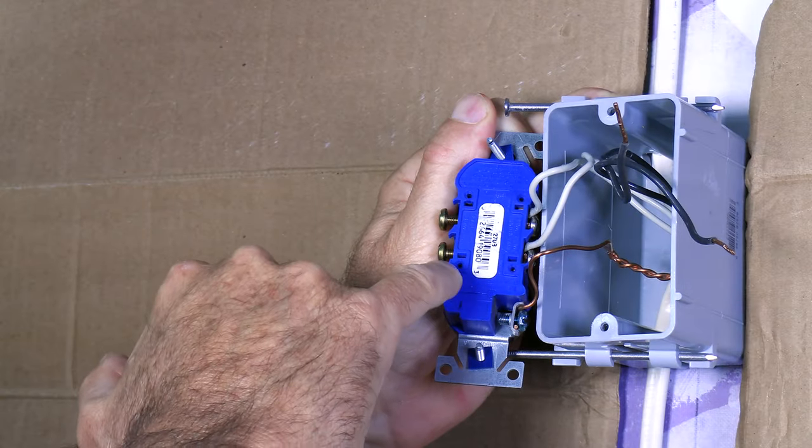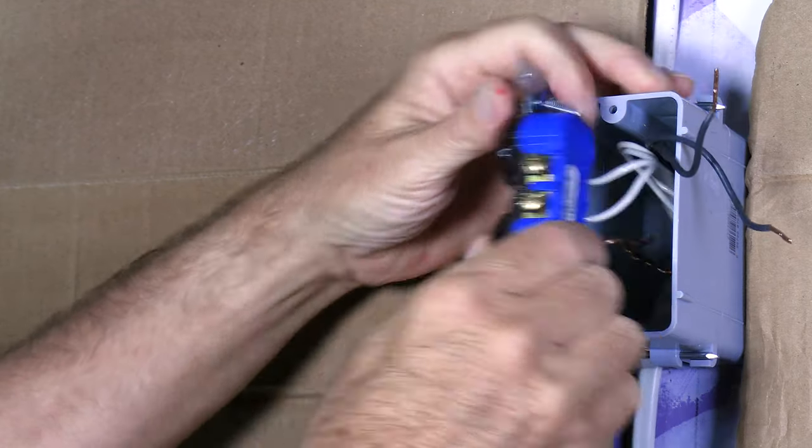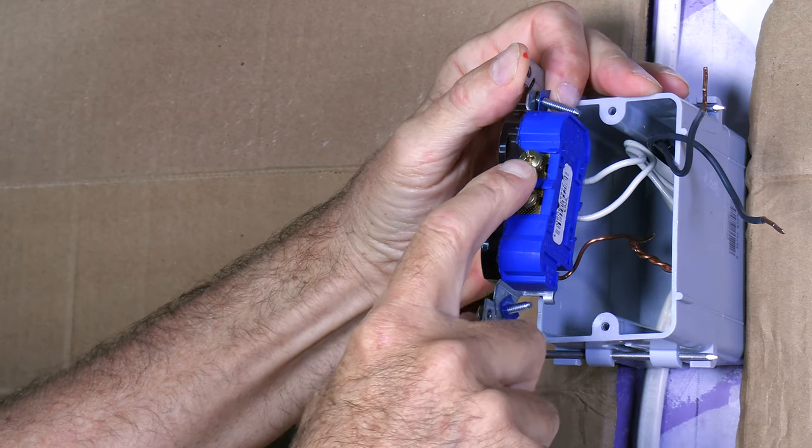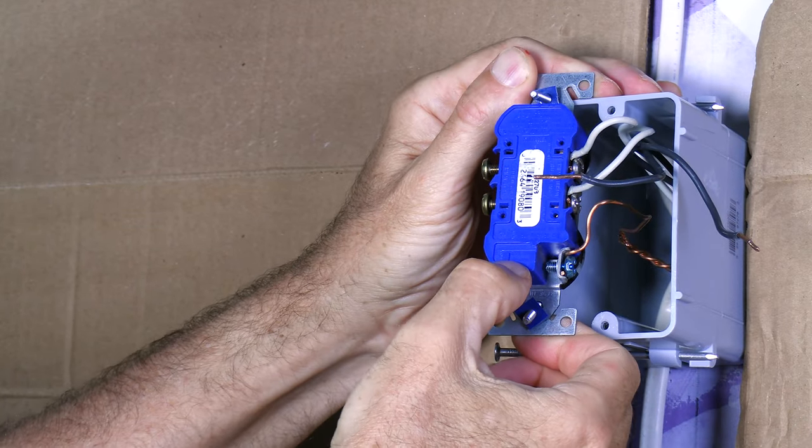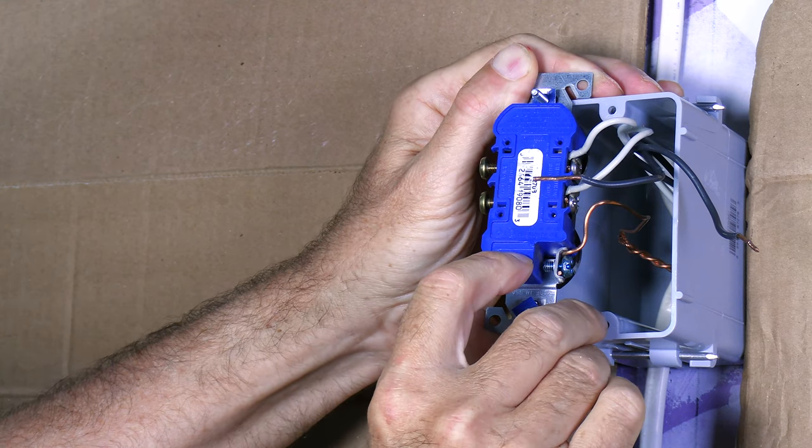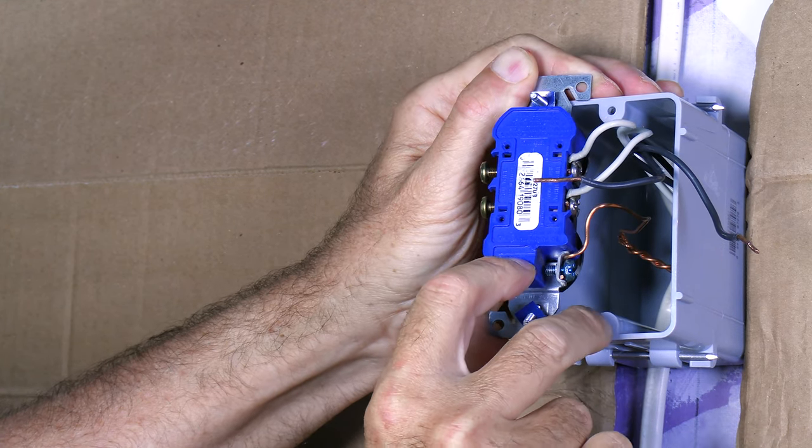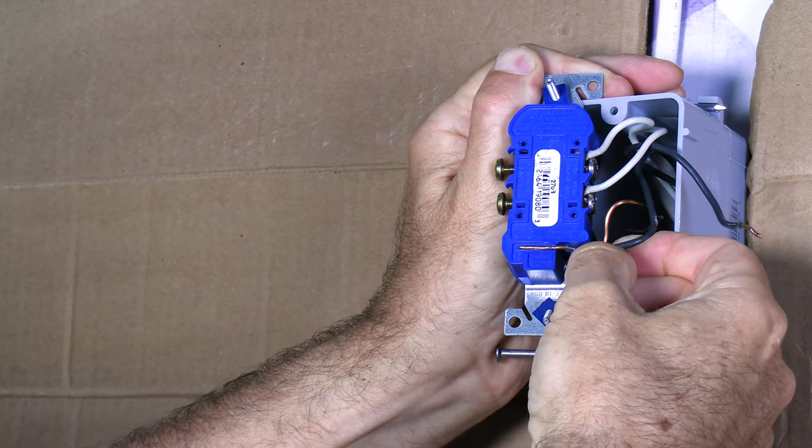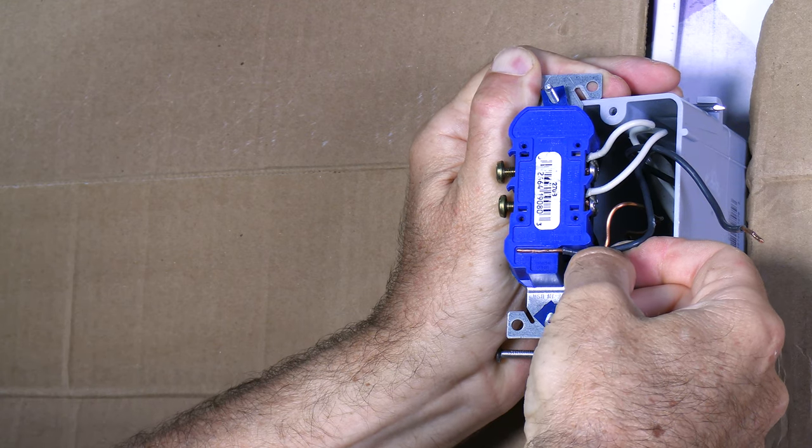Okay. So instead of using the stab lock thing in the back of the plug, I like to put the wire around the screws. To me, that makes a much better connection and it's safer. So to make sure that you get the wire peeled back the right amount, you may not know this, but if you look at the back of the plug, this plug is upside down, but if you can read this, it says right here, strip gauge. I don't know if you knew about that or not, but it kind of gives you a guideline of just how much to strip that back. See, that's just about right, right there.